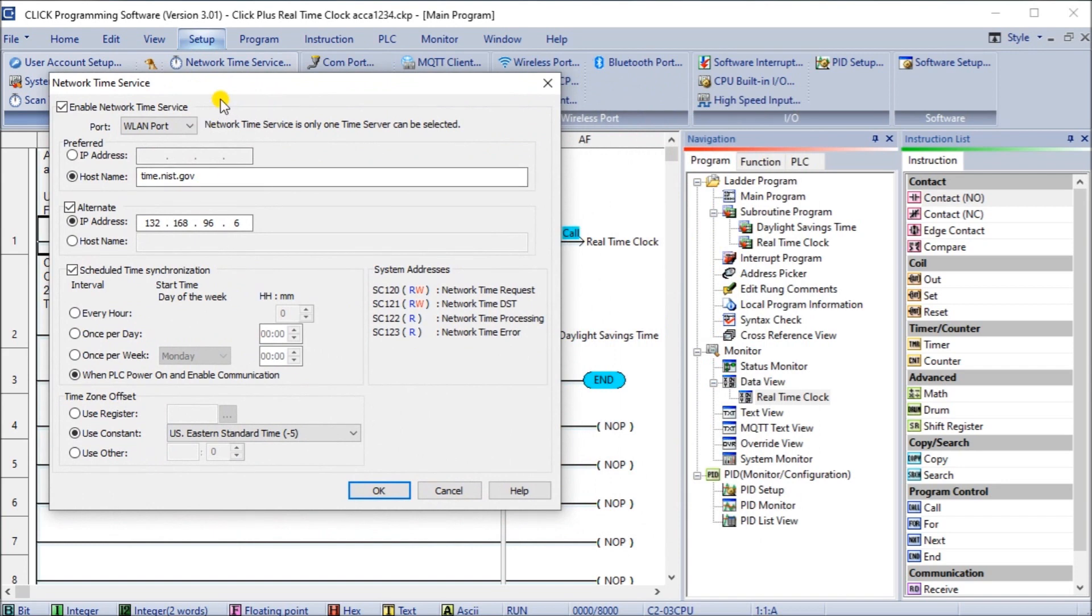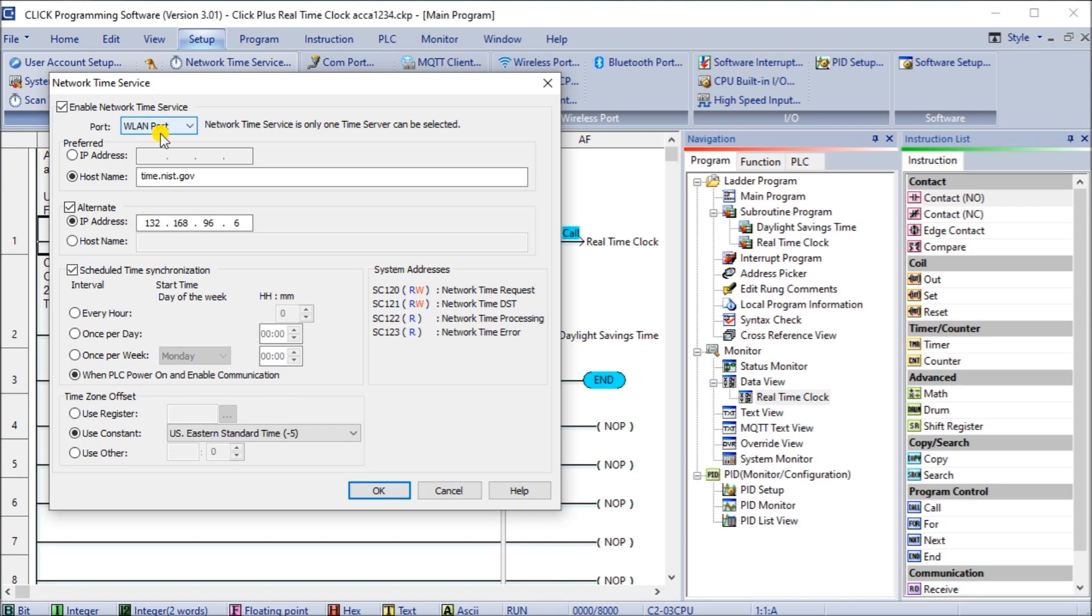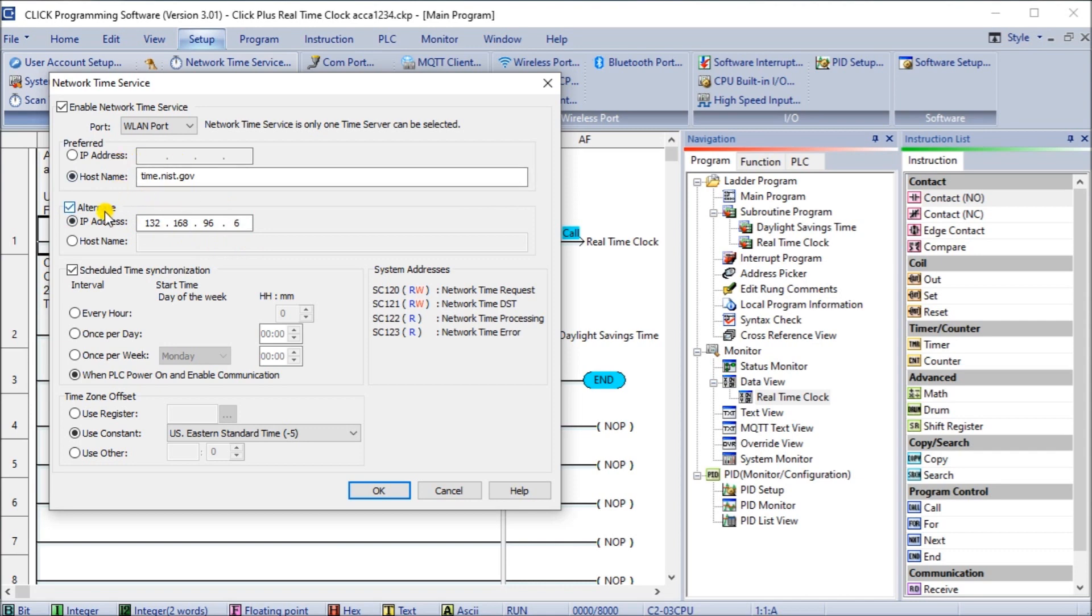Once we do, you'll see that we actually have an option at the top. We actually enable it first, then we can set the port that we have on here. In this particular case I'm using the Wi-Fi LAN port which is on the Click Plus on the C2-03 CPU unit, and we have the preferred host which is time.nist.gov and our alternative address for that, and we just use one of the IP addresses for this same website. Now you don't have to use an alternative or you can use a completely separate one if you wish.